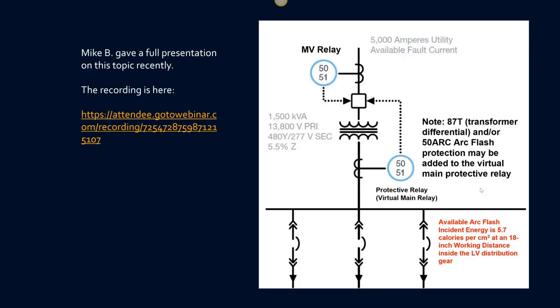And again, if that primary device is a switch over breaker, in this case, if we were to add a switch to this one line, you open the switch, you ground the switch, so it's a 3-position switch. So in a matter of 5 seconds, you've opened, you've grounded, you've locked out, tagged out. All you have to do now is verify absence of voltage and go to work. You've established an electrically safe and grounded working condition.